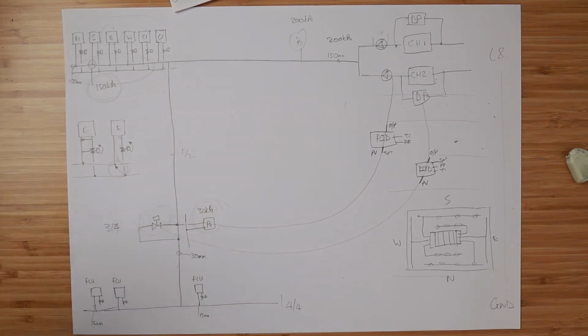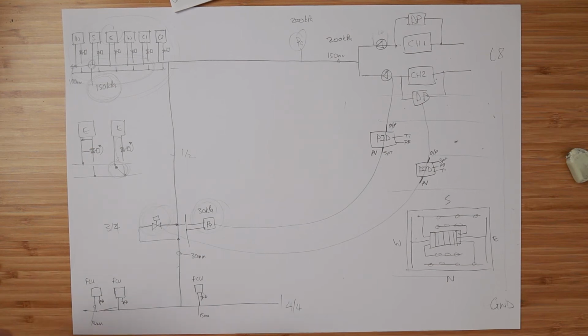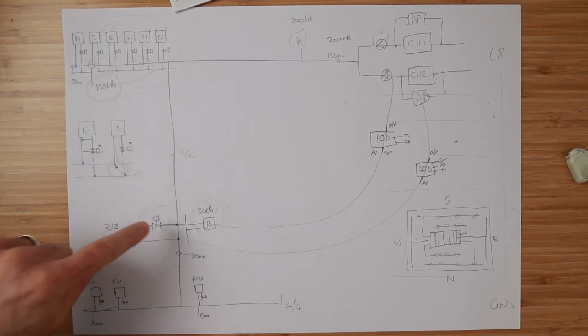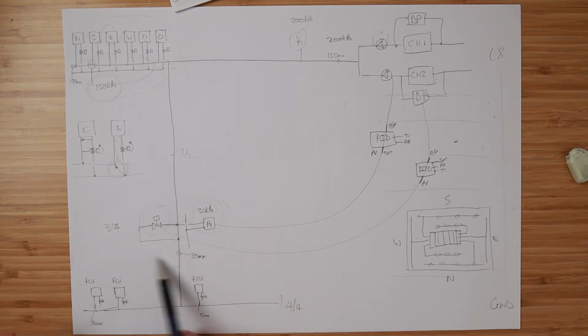So the design of where you put your system pressure transmitter, it's not just about how well the system will control. How will you have stable control to the pumps and reliable control and so on. It actually has a lot to do with where do you want to have the right pressure. Do you want to have beautiful pressure down here? Or do you want to have good pressure where the main equipment is?